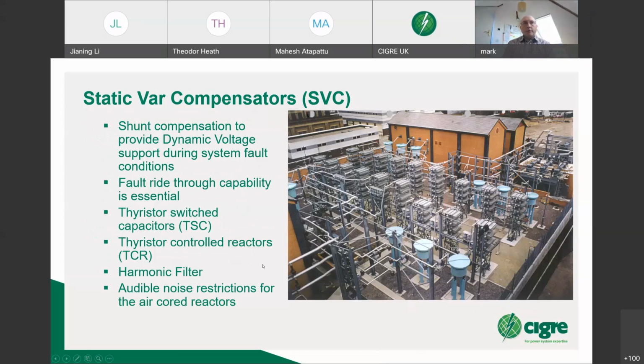These are a traditional form of dynamic shunt compensation, which use capacitors and inductors coupled with power electronics to facilitate a response usually during a post-fault condition. These typically use thyristors, which switch in blocks of capacitance, backed off with a thyristor controlled reactor, allowing for fine control so you get a variable amount of VARs injected, positive or negative, depending on the network conditions.